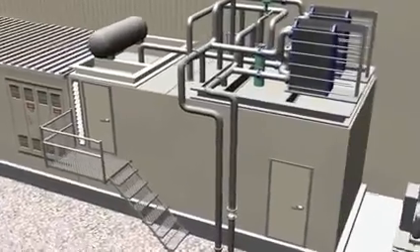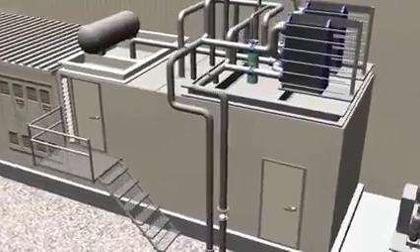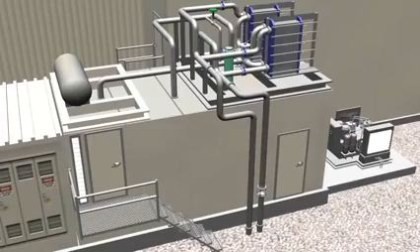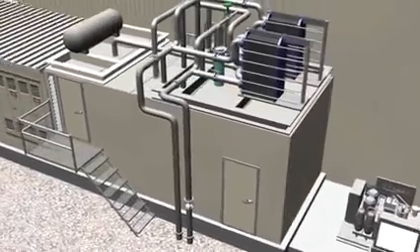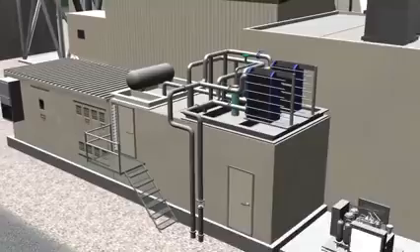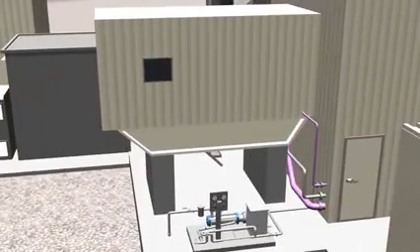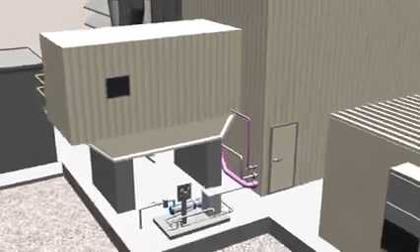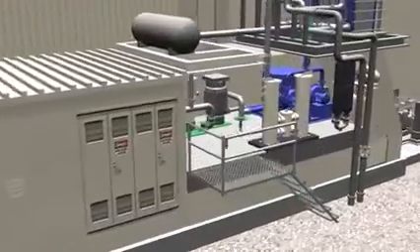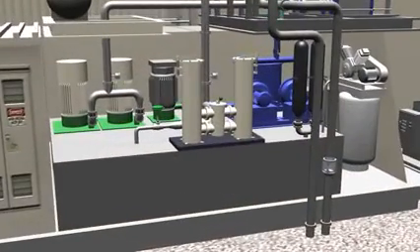The combustion turbine mechanical package houses the components that make up the lubricating oil system. The lubricating oil system provides an uninterrupted supply of filtered oil at the required temperature and pressure to lubricate the combustion turbine bearings. Lubrication is also provided to the starting package bearings and is used as the working fluid for the starting package torque converter. The lubricating oil reservoir occupies most of the lower part of the mechanical package.